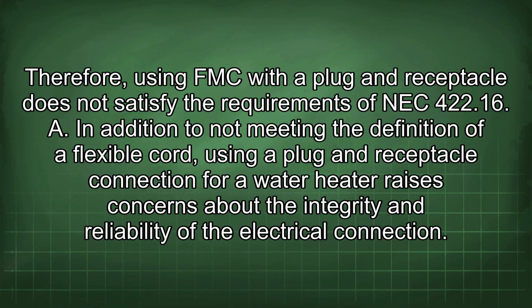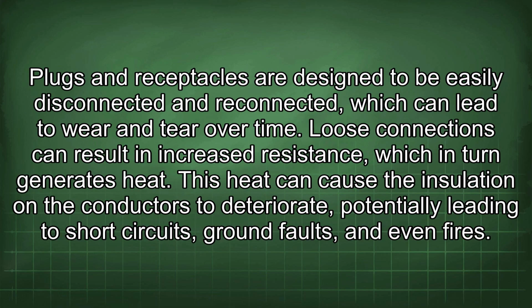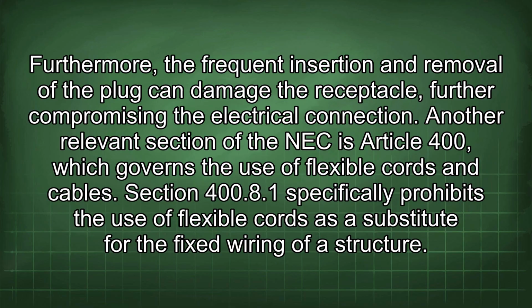422.16. In addition to not meeting the definition of a flexible cord, using a plug and receptacle connection for a water heater raises concerns about the integrity and reliability of the electrical connection. Plugs and receptacles are designed to be easily disconnected and reconnected, which can lead to wear and tear over time. Loose connections can result in increased resistance, which in turn generates heat. This heat can cause the insulation on the conductors to deteriorate, potentially leading to short circuits, ground faults, and even fires. Furthermore, the frequent insertion and removal of the plug can damage the receptacle, further compromising the electrical connection.